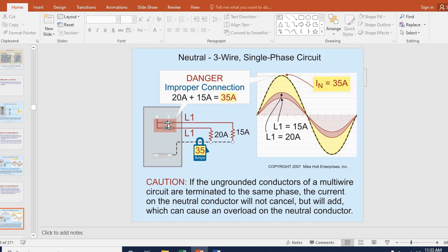But if they're on the same circuit, L1, off that one lead, then you got a 20 amp breaker and a 15 amp breaker, and you loaded with some kind of heat or whatever was pulling 35 amps. If they were loaded up, then you would have 35 amps on your neutral. A lot of times you can go to a neutral, and if it's been hot, that's what they've done. So be careful. A lot of times I just pull one neutral to one phase, and that way I'm covered. But if you go to hooking up several circuits and using one neutral, be careful about that.